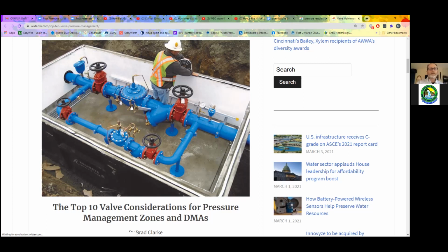And when it's topped out and opened up as full as it'll go, if it's not enough supply, the pressure gauge will start to fall, and the second valve will start to open to compensate and to fill in behind the downstream pressure. So for instance, peak demand, or maybe this valve will only open in a fire. Typically not, they would have a fire protection system in there. But you can see that gives great flexibility. Smaller valve, much easier to control for small demand and flow. And then as flow increases, perhaps in the summertime, this valve will open.